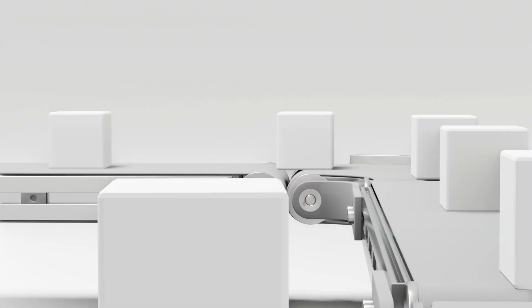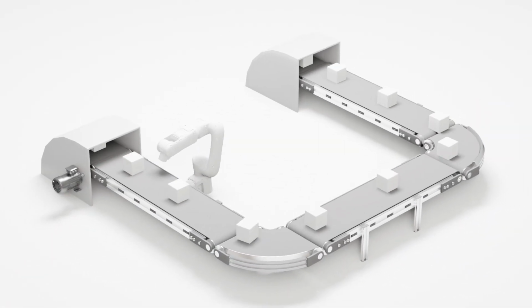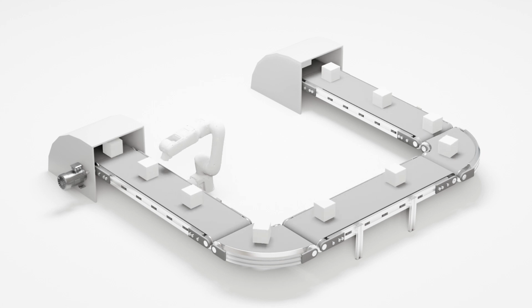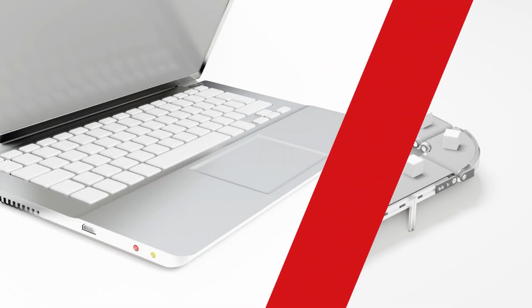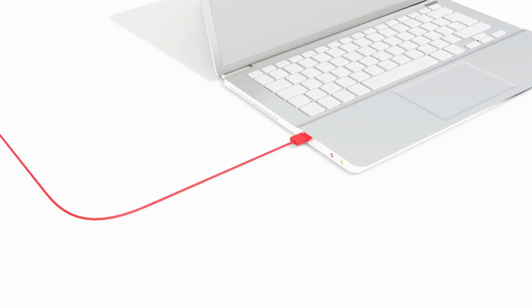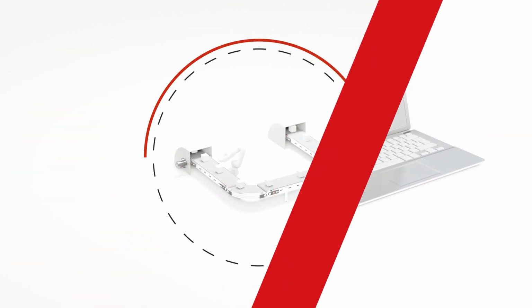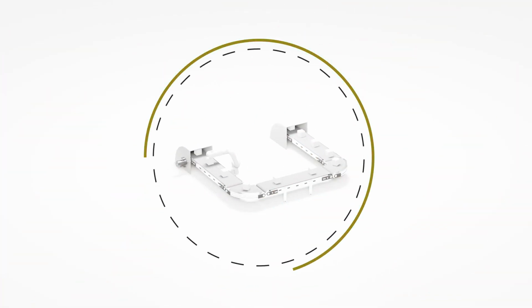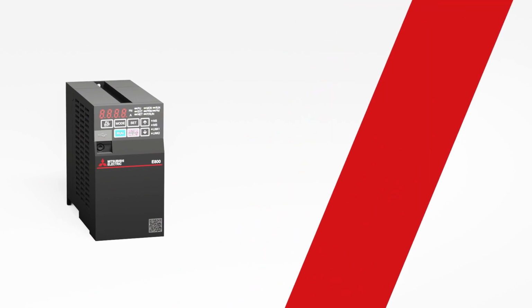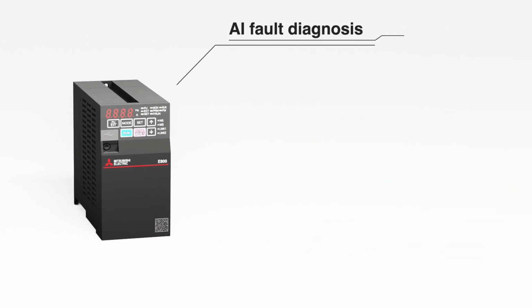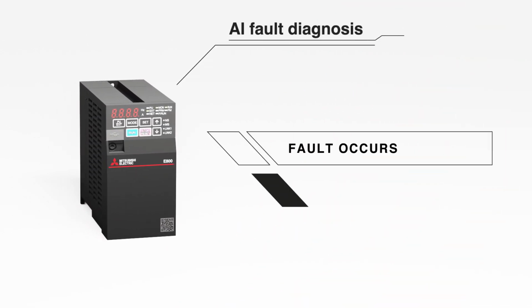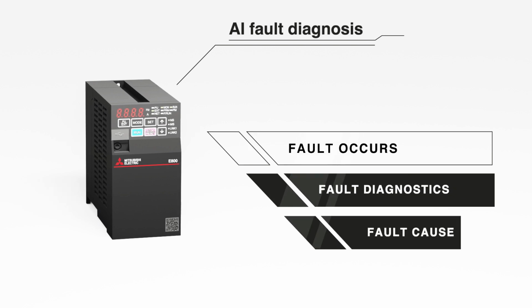Factory equipment should be easy to diagnose and have the ability to inform about potential issues in advance. Let's start with the fact that inverters can be powered from a laptop's USB, so we do not need to start the power circuit to be able to perform maintenance. The typical way of diagnosing problems is: fault occurs, fault diagnosis, fault cause.